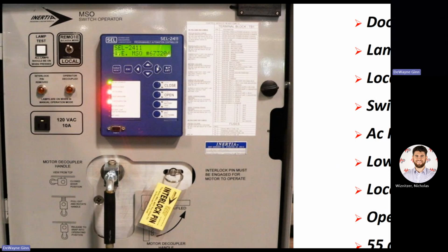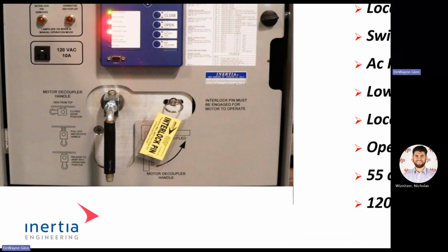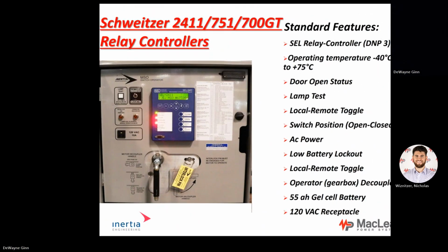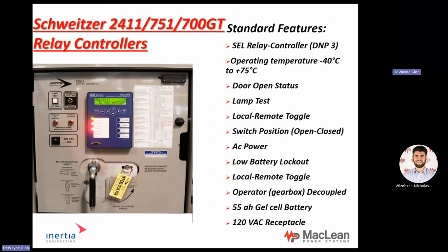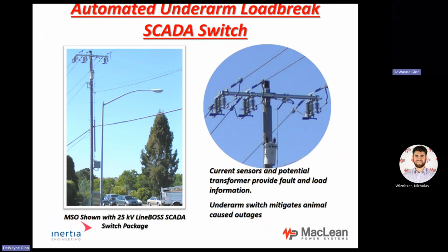This one is designed for a smart switch, and we'll talk about that in a minute. Right there's where I decouple, and there's again that interlock pin. So let's go to the next slide. If you look at the switch on the right, it's got current sensors on it. I can put current and voltage sensors on it. What happens if I lose current or voltage? It senses it and it can go back to that Schweitzer relay.